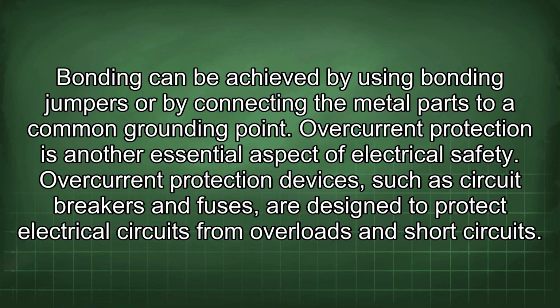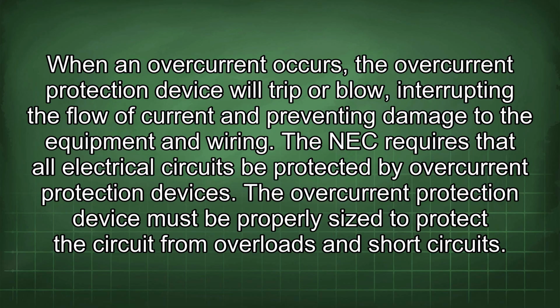Overcurrent protection is another essential aspect of electrical safety. Overcurrent protection devices, such as circuit breakers and fuses, are designed to protect electrical circuits from overloads and short circuits. When an overcurrent occurs, the overcurrent protection device will trip or blow, interrupting the flow of current and preventing damage to the equipment and wiring. The NEC requires that all electrical circuits be protected by overcurrent protection devices. The overcurrent protection device must be properly sized to protect the circuit from overloads and short circuits.